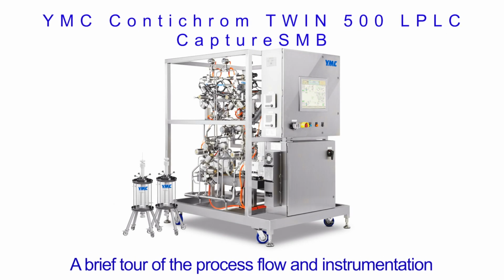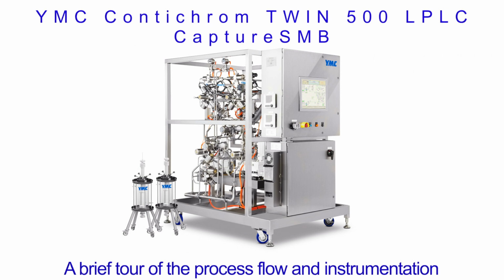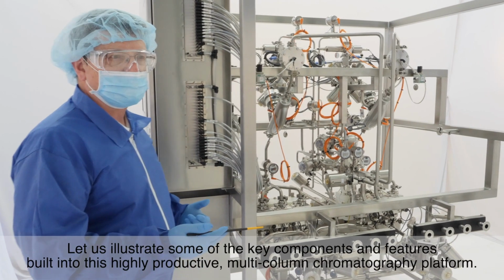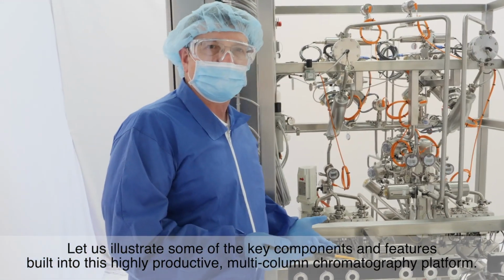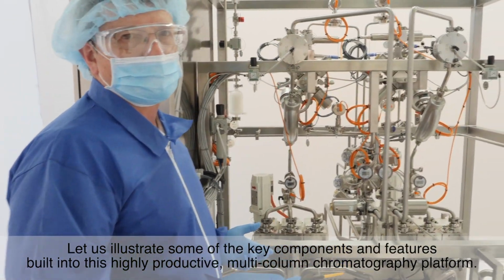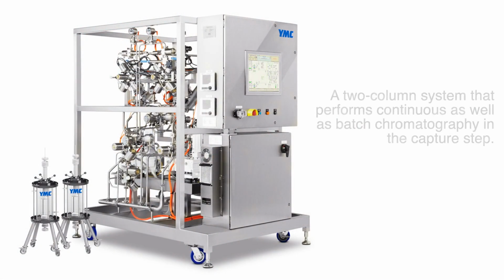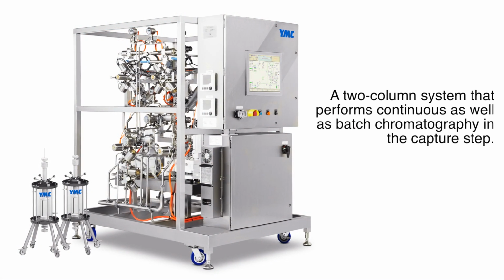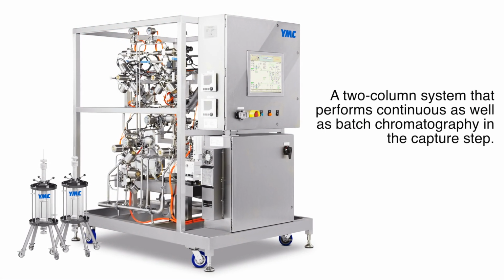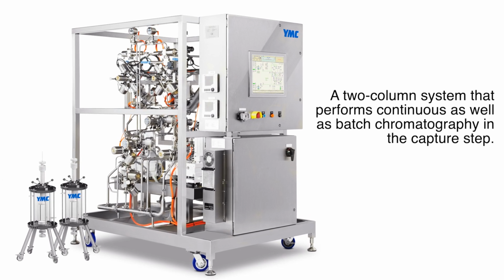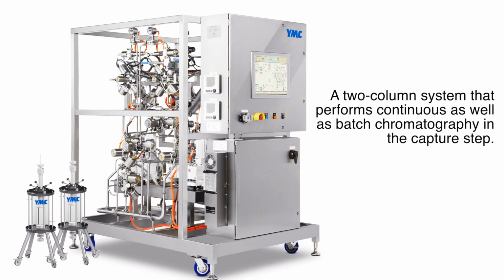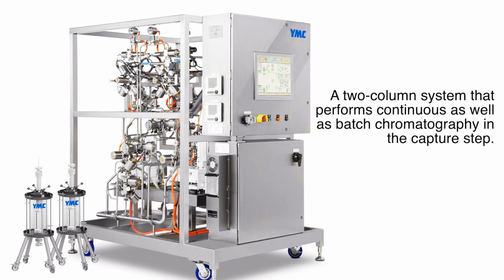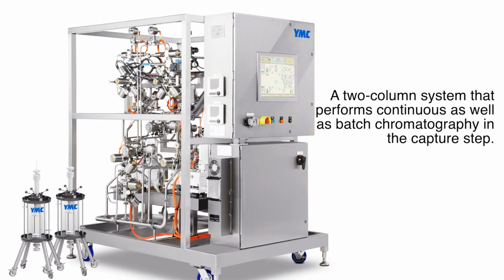Welcome to a tour of the YMC Contichrom Twin LPLC system. Let us illustrate some of the key components and features built into this highly productive multi-column chromatography platform. This system is designed for the continuous purification of biopharmaceutical therapeutic proteins, such as monoclonal antibodies, using two columns. It also has the capability of performing conventional single-column batch operations.